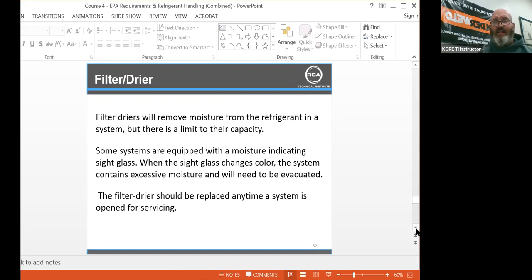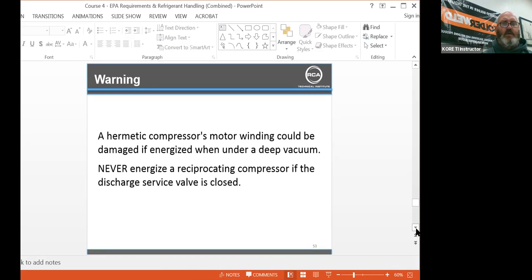There are some sight glasses out there that have no indicator. They're very old systems that actually had a sight glass on one side and a sight glass on the other, and you put a flashlight in the back, and that's how you check your liquid level. So you have to make sure of that. The filter dryer should be replaced anytime a system is open for being serviced. Hermetic compressor motor windings could be damaged if energized in a deep vacuum. Never energize a recip if the discharge valve is closed. Big boom.